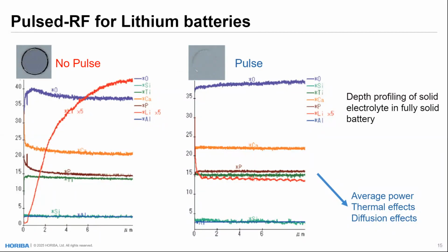With the Pulse RF system, we control the sputtering rate while we keep our intensity of light maximum, which means if your sample is sensitive to the plasma, to the temperature, to sputtering, we can reduce the damaging effect of plasma while keeping the intensity of light the same and do the analysis as it should.